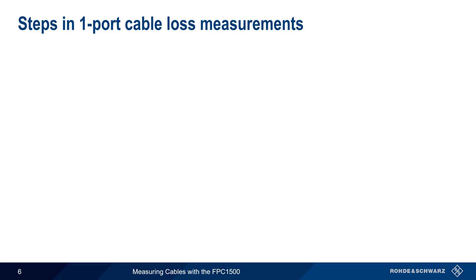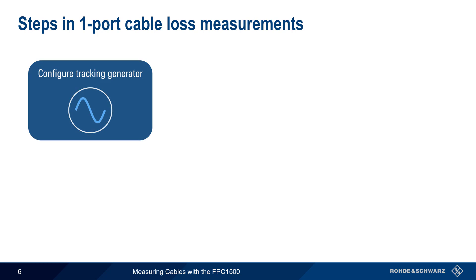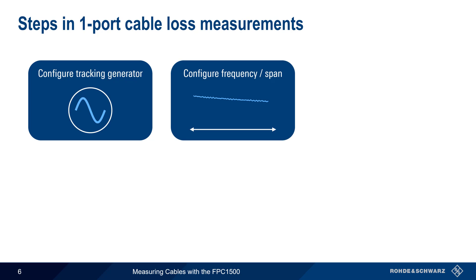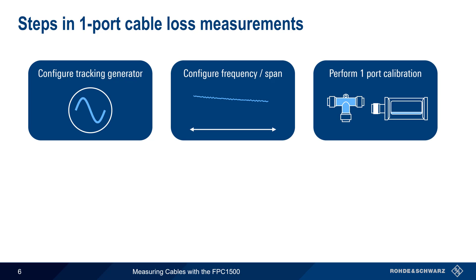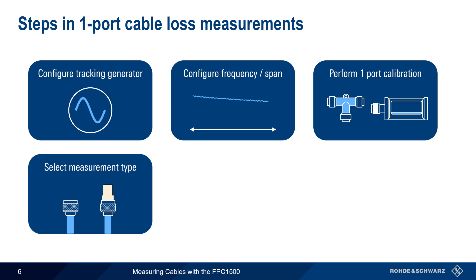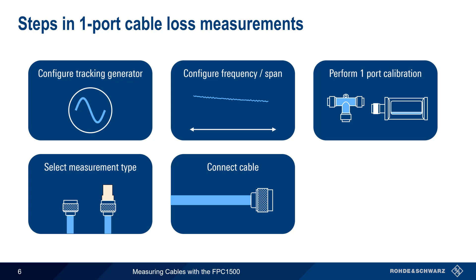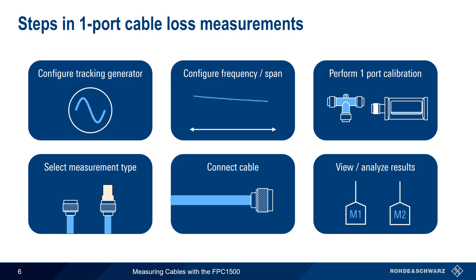There are six basic steps in making one-port cable loss measurements: configuring the tracking generator, configuring the frequency and span, performing a one-port calibration, selecting the cable measurement or termination type, connecting the cable under test, and viewing and/or analyzing the results. In the next few minutes, we'll go through each of these steps.